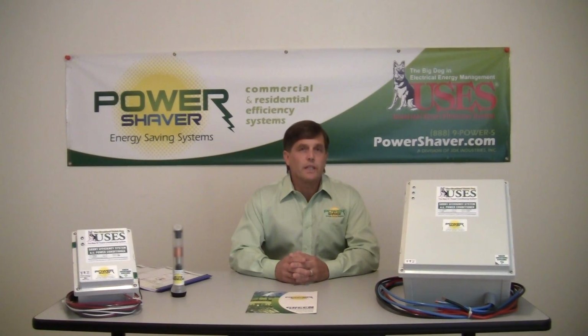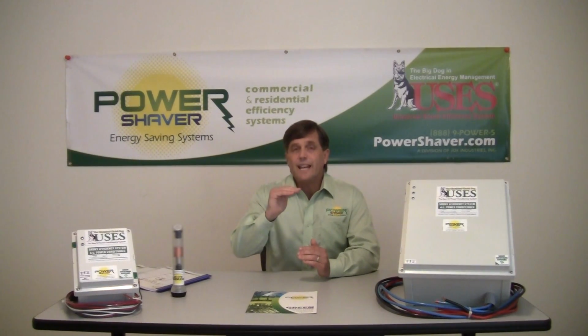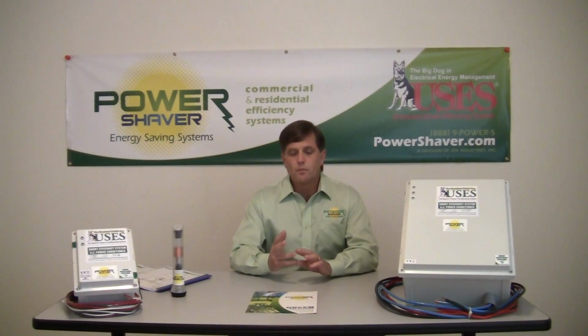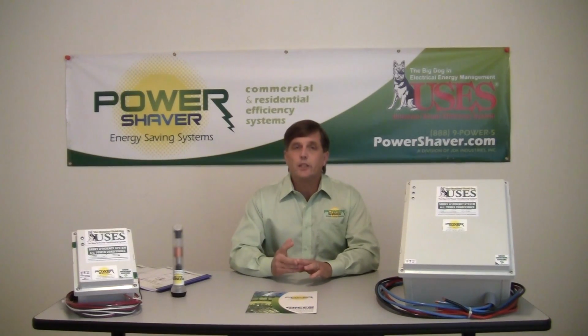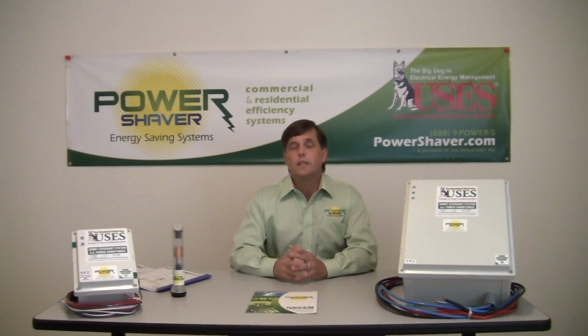The methods incorporated in the device are as follows. Magnetic phase balancing through our proprietary choke system, which reduces waste on the high voltage phases by shunting them over to the low voltage, increasing the average voltage and current. This reduces waste, thus reduces demand. It also, specifically in inductive loads, reduces the internal warble or vibration from out of balance phases, which reduces friction and heat attributable to that, which will then let the motor last longer in industry.